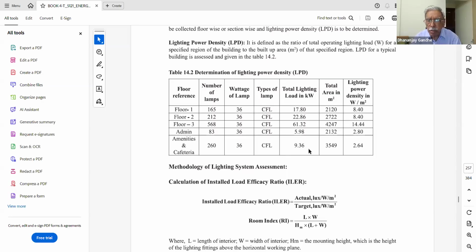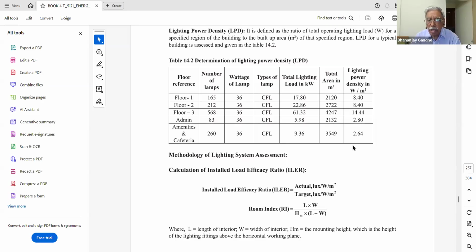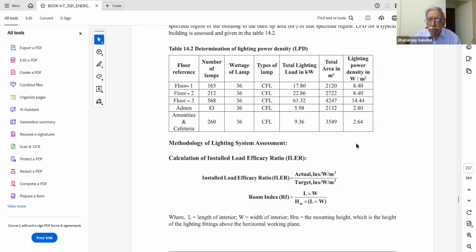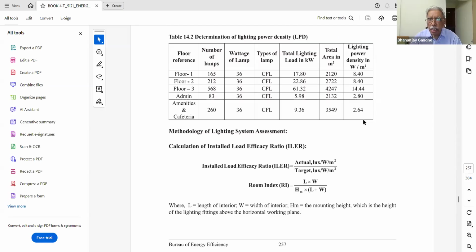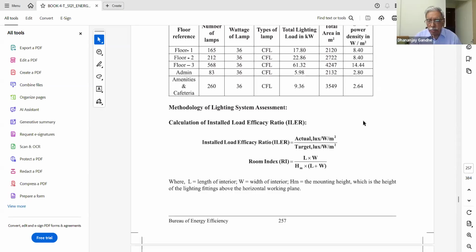So floor 2, similarly, the lighting load is 22.86 kilowatt, that is, expressed in watts, 22,860, divided by area 2722. The answer is 8.4 watts per m square. Similarly, also calculate for floor 3. Here the lighting power density works out to 14.44. Similarly, for the administration area, it works out to 2.8, and for the amenities it works out to 2.64.